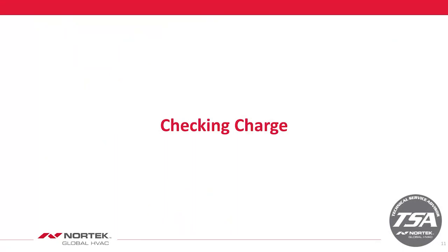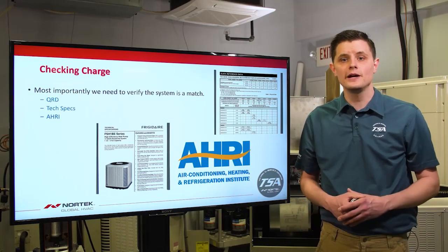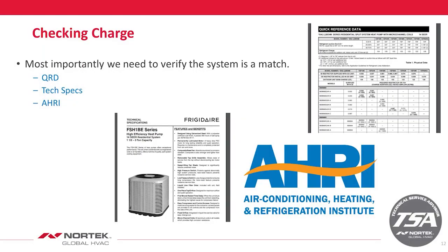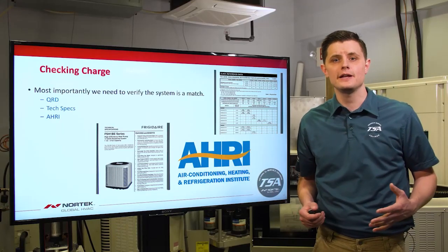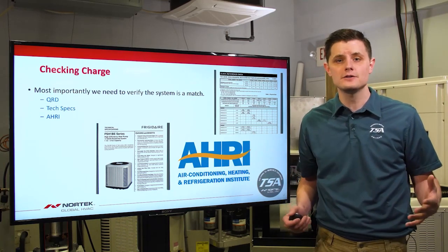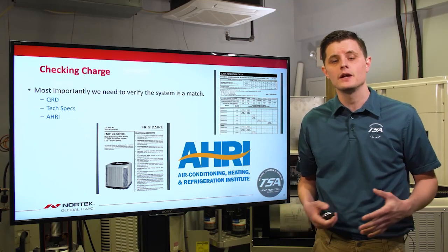Now let's look at checking charge. First, make sure the system you're working on is a proper match. There are three ways to verify: the QRD on our literature library, the tech spec of the condenser, or the AHRI website. On the AHRI website, use a base model number — if you get too detailed with the full model number it may limit the matches that auto-populate. Start with the base series number and branch off from there.